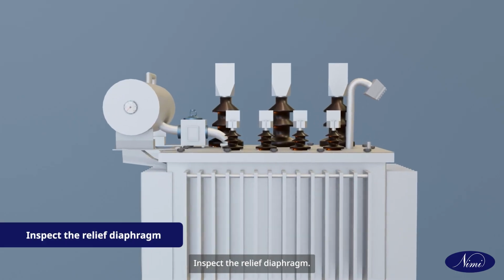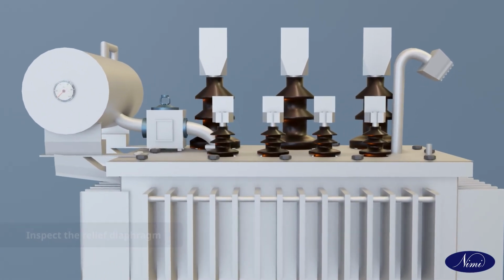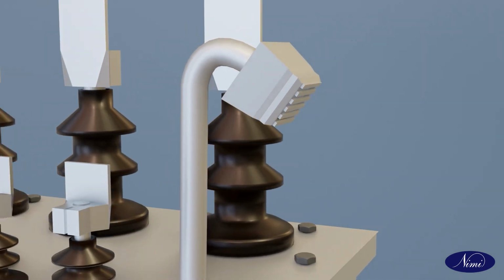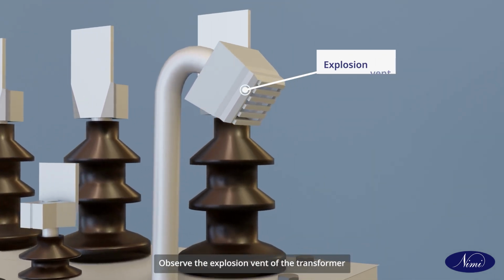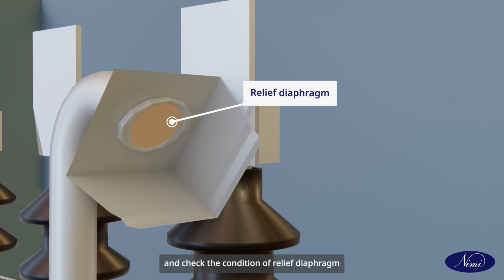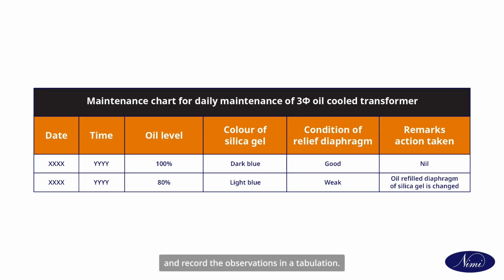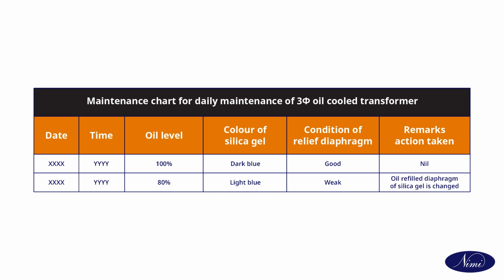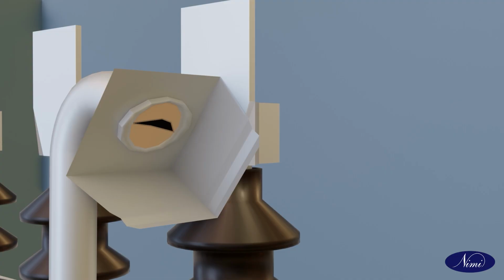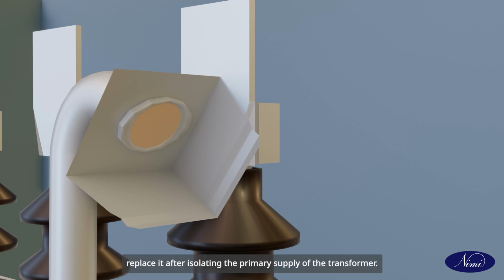Inspect the relief diaphragm. Observe the explosion vent of the transformer and check the condition of the relief diaphragm and record the observations in a tabulation. If it is cracked or broken, replace it after isolating the primary supply of the transformer.